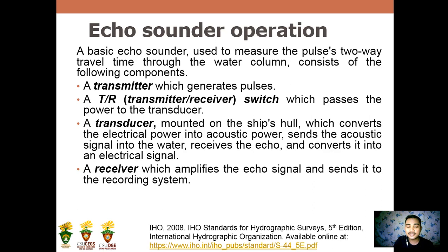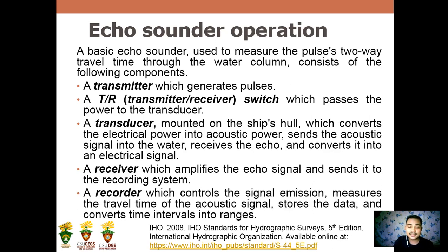The next is the recorder, which controls the signal emission and measures the travel time of the acoustic signal. It stores the data and converts time intervals into ranges.